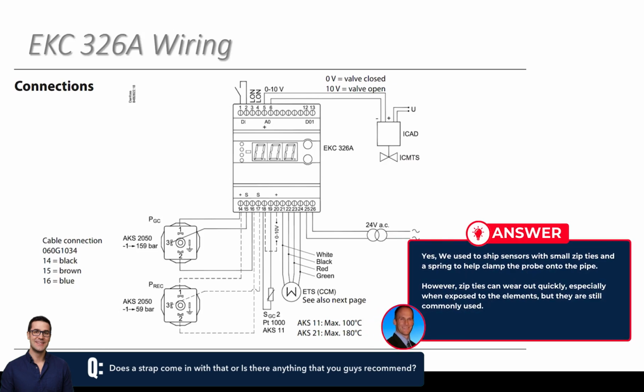Yeah, I think at one point, I don't know if we still do or not, but we actually shipped them with some small zip ties in a bag with the sensor. It has a small spring on the top of it and the curvature to the probe that helps it fully clamp onto the pipe. Yep. But I'd say zip ties are what I agree with you. Especially if you're on the roof, it's going to be exposed to some elements, and that zip tie will wear out pretty quickly. But that's probably what we see the most of used to hold it down.